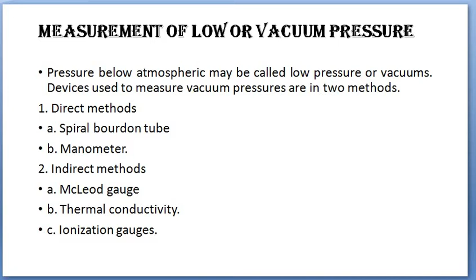Let's go through the McLeod gauge a bit quickly. The principle of working of the McLeod gauge is the compression of a sample of the low pressure gas to a pressure sufficiently high to read with a simple manometer. Since this is for low or vacuum pressure, you compress it to a pressure high enough, using the simple manometer, to pressurize and compress it, and then read the result.